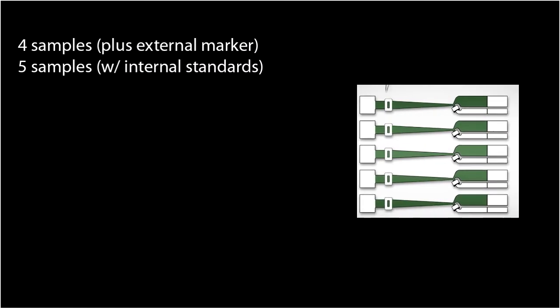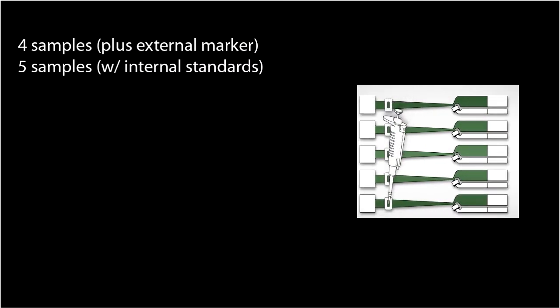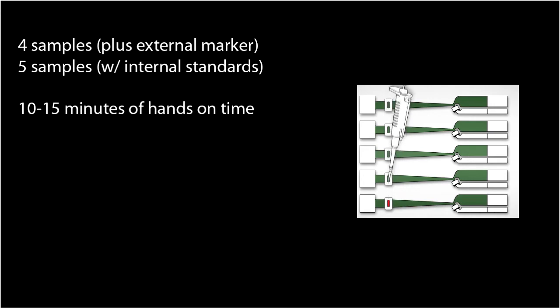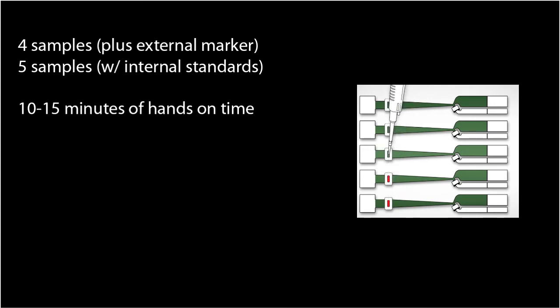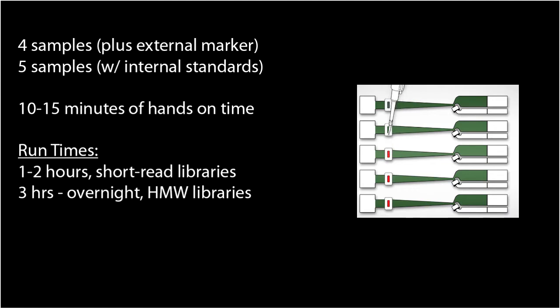Processing a gel cassette with 4 or 5 DNA size selection samples should take about 10 to 15 minutes of hands-on time. Typical run times for short read libraries are 1 to 2 hours. Pulsed field protocols for high molecular weight DNA size selection can require several hours or overnight.